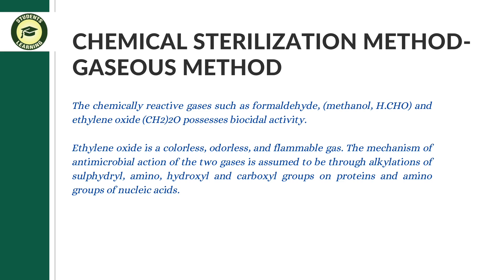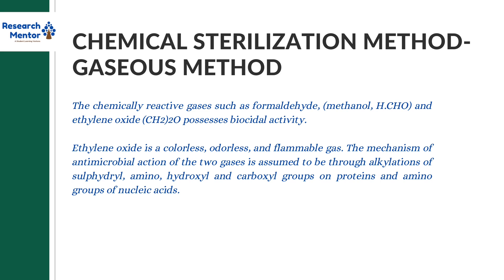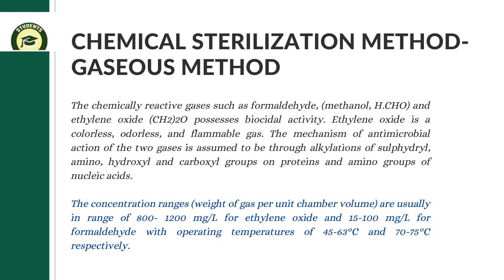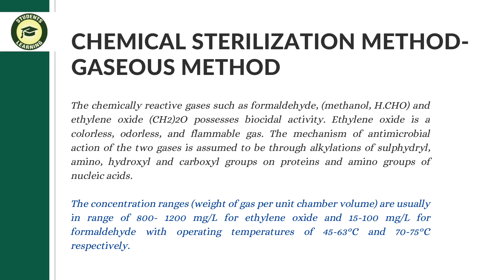The chemical sterilization method — the gaseous method — uses chemically reactive gases such as formaldehyde and ethylene oxide, which possess biocidal activity. Ethylene oxide is a colorless, odorless, and flammable gas. The mechanism of antimicrobial action is through alkylation of sulfhydryl, amino, hydroxyl, and carboxyl groups of some proteins and amino groups of nucleic acids. Concentration ranges are usually 800–1,200 milligrams per liter for ethylene oxide and 15–100 milligrams per liter for formaldehyde, with operating temperatures of 45–63°C and 70–75°C respectively.